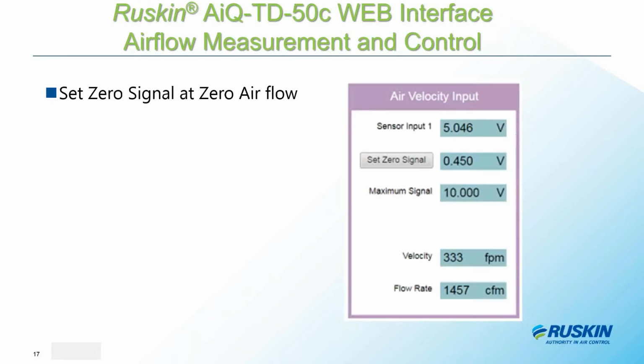And then the last thing that has to be done is with the airflow set at 0 flow, you will see displayed up in here the actual voltage that the air measurement device is producing at 0 flow, and so you then set the 0 signal. In this case, you're seeing that the 0 signal is almost half a volt, and so from this point forward, 0 airflow measurement is created anytime we have 0.45 volts, and then anything more than that becomes our measured airflow rate. So that's how you scale it and get it configured to accurately represent this information.